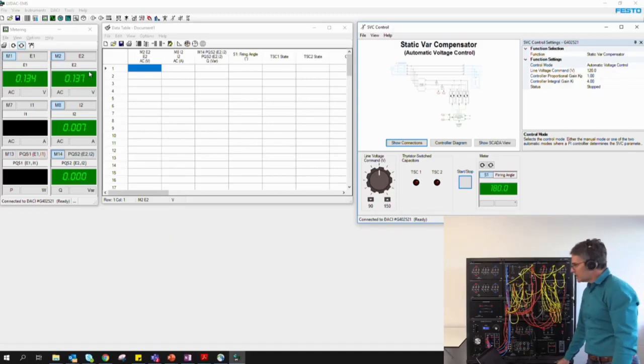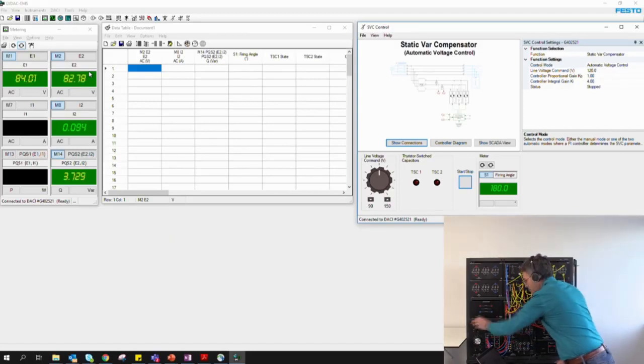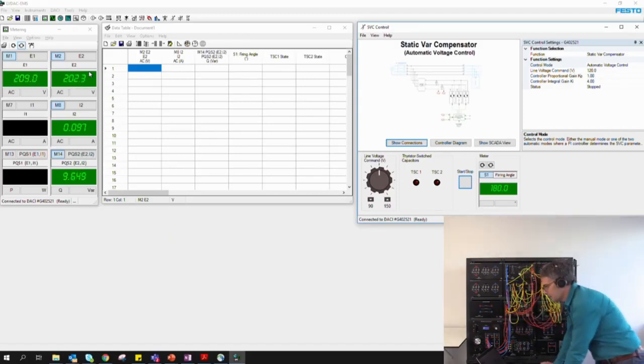Let's power up the system and see how the SVC achieves control. Right from the start, with the low load we have right now, 1200 ohms per phase, we don't have the expected voltage at the receiving end since the SVC is not in the circuit yet. By the way, the voltage we see here is the line voltage, while the command specified is the phase voltage, and that's the difference that explains the gap you see.